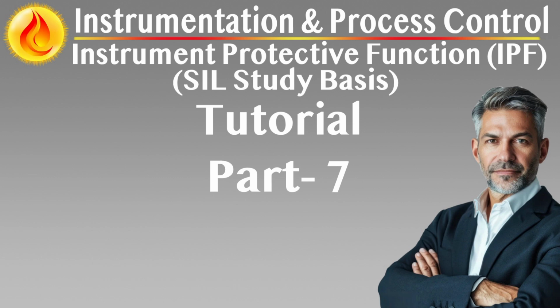Testing is not a one-time event, but a recurring requirement throughout the life of the IPF. It supports commissioning, routine proof testing, diagnostics, post-maintenance verification, and periodic revalidation of functional safety performance. Objectives of IPF testing: confirm functional integrity. Ensure the full IPF loop detects the correct initiating condition and executes the expected response reliably and within the defined process safety time.